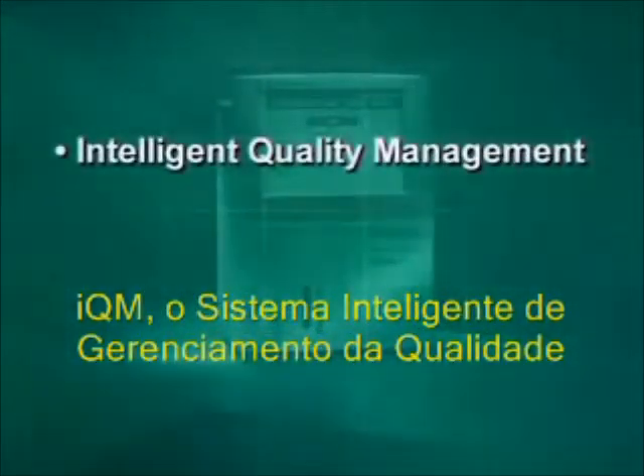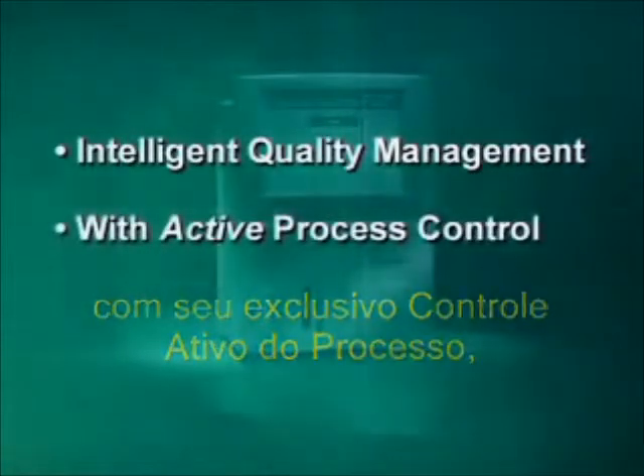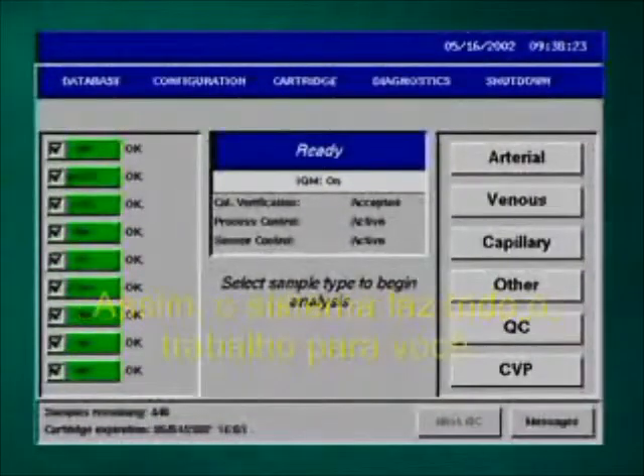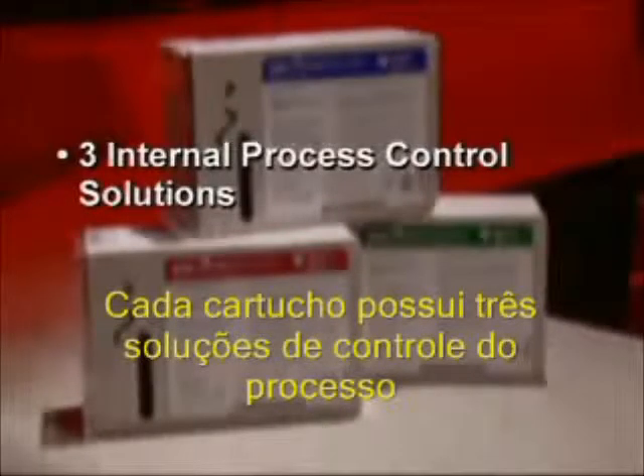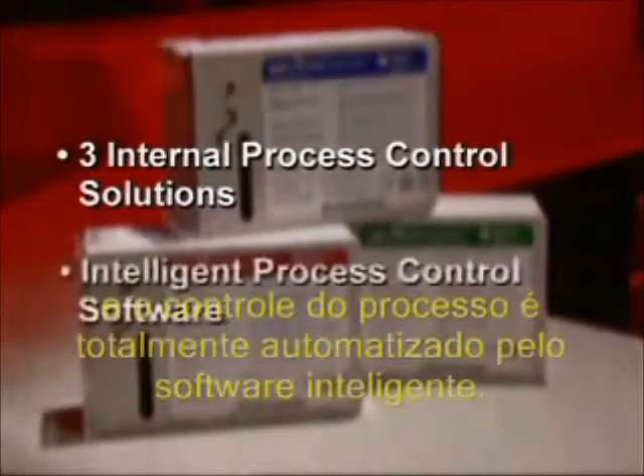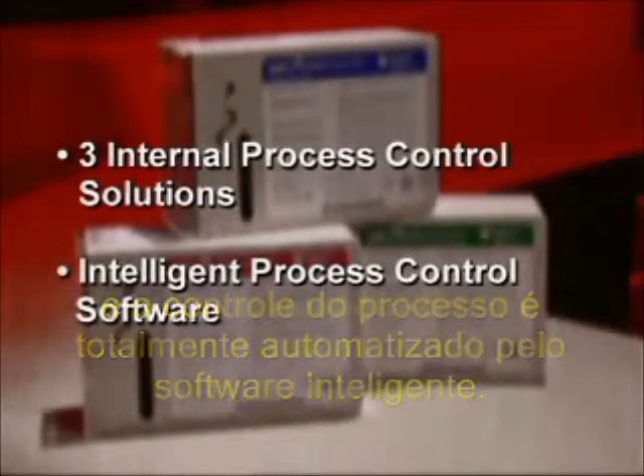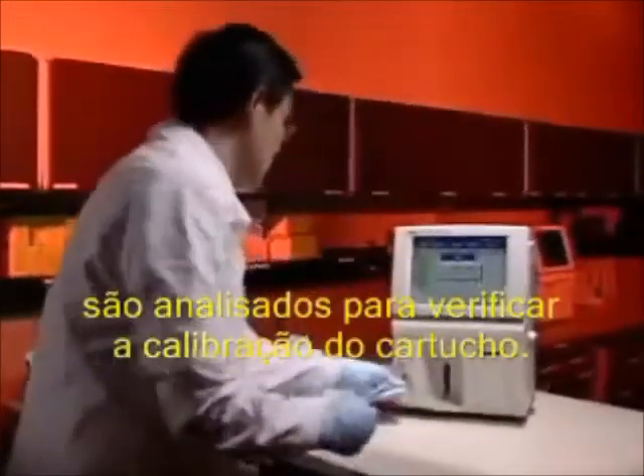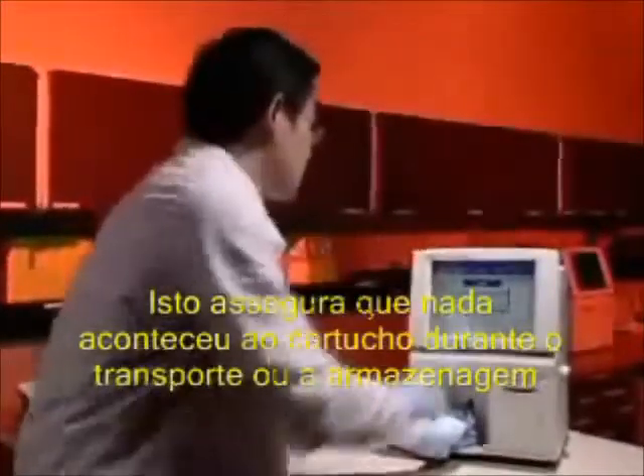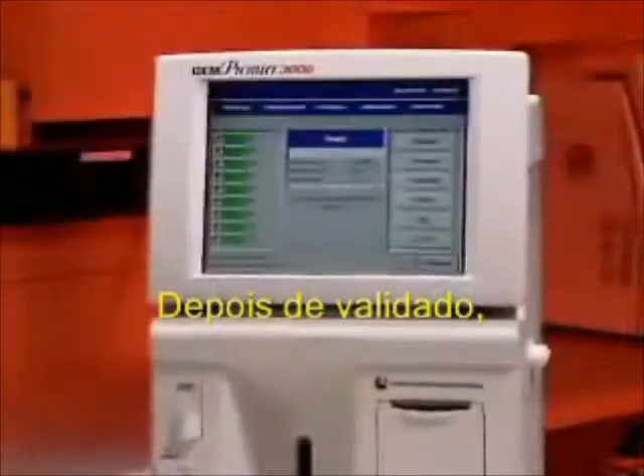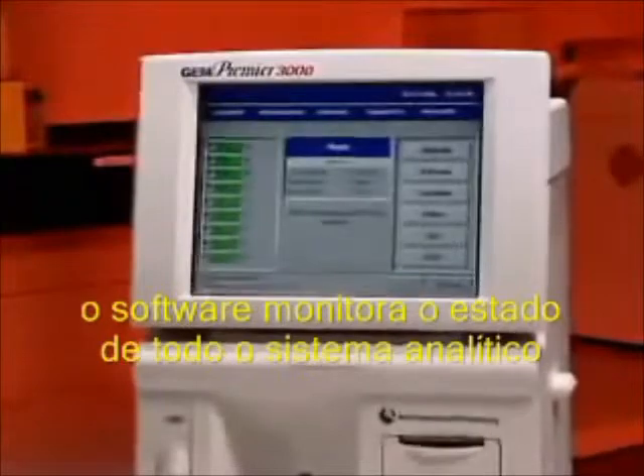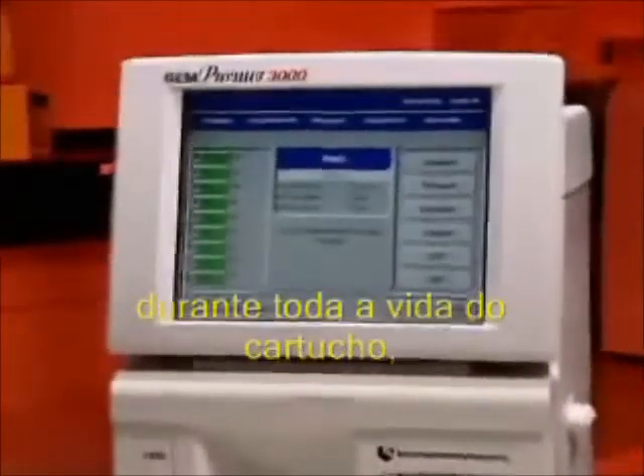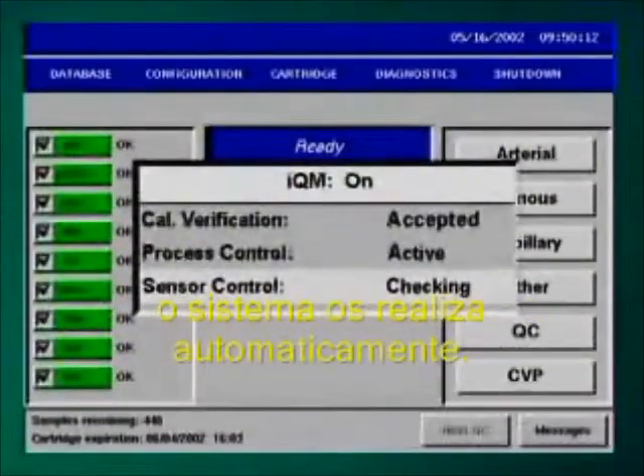IQM, the Intelligent Quality Management System, with its unique active process control, automatically ensures that the GEM Premier 3000 provides accurate and precise results at all times, so you can let the system do the work for you. Each cartridge has 3 internal process control solutions that are manufactured to reference standards and is fully automated by the Intelligent Process Control software. After initial warm-up, external calibration validation products, CVP, are analyzed to verify the cartridge calibration, so you can be sure nothing has happened during shipping or storage. Then, once validated, the analyzer automatically monitors the status of the analytical system throughout the life of the cartridge. And if it needs adjustments, the system automatically does it for you.